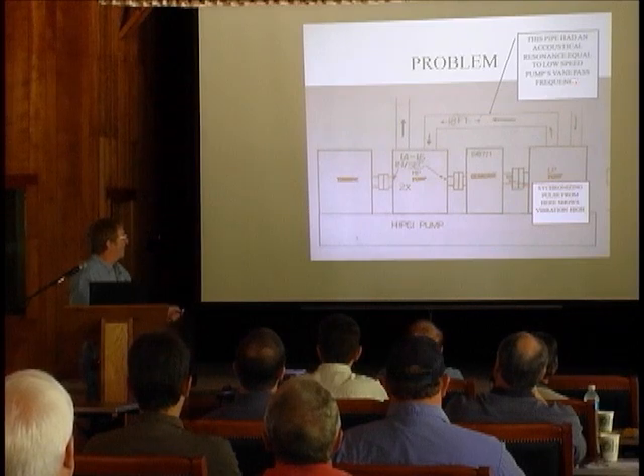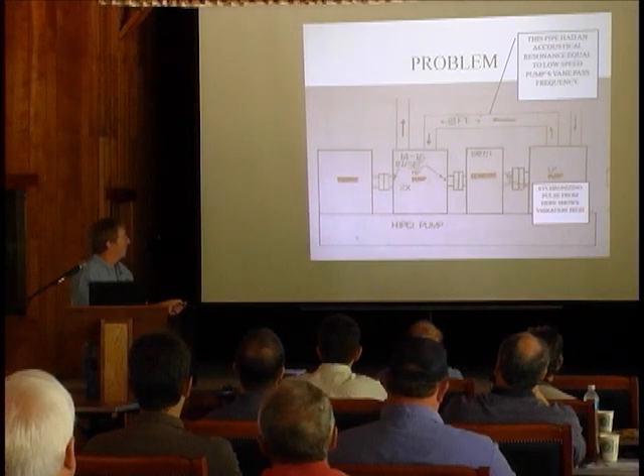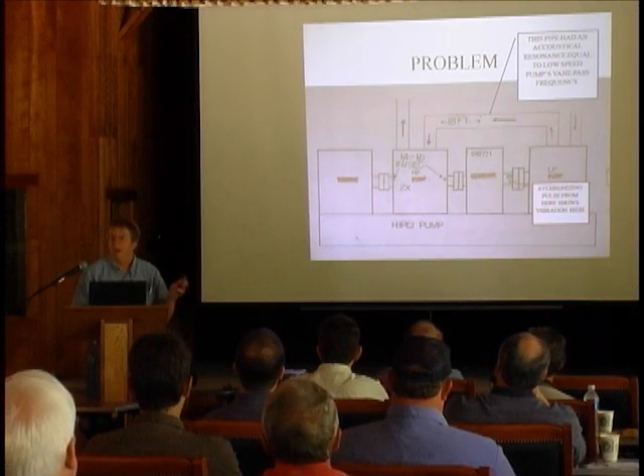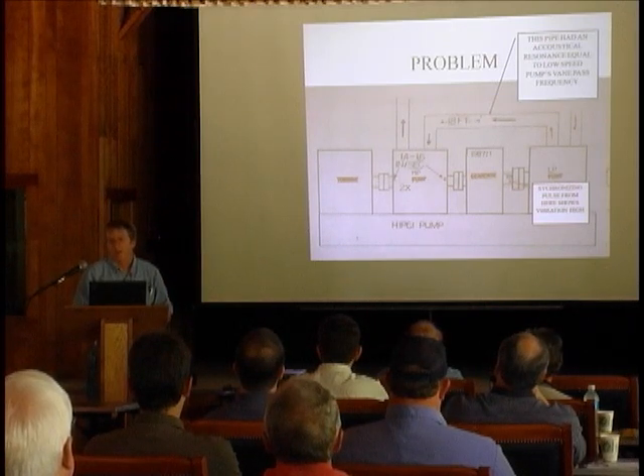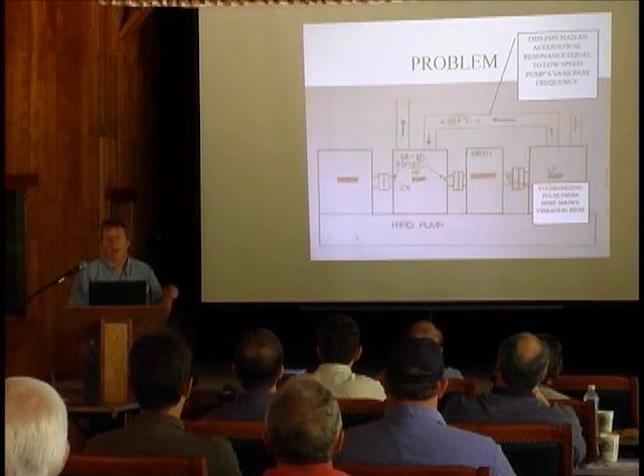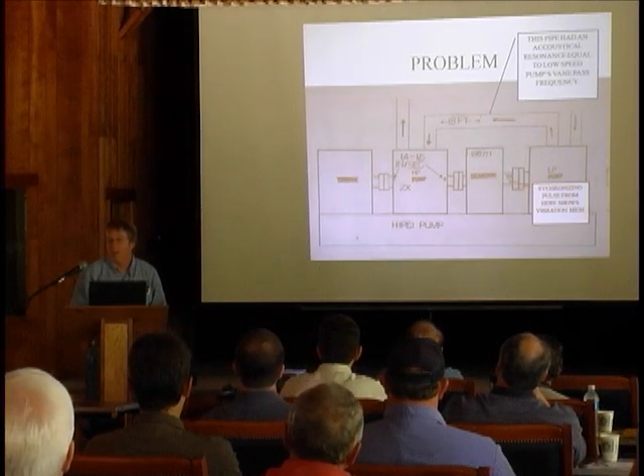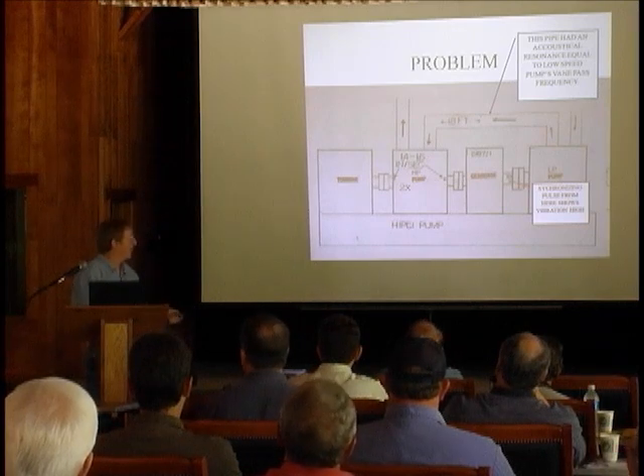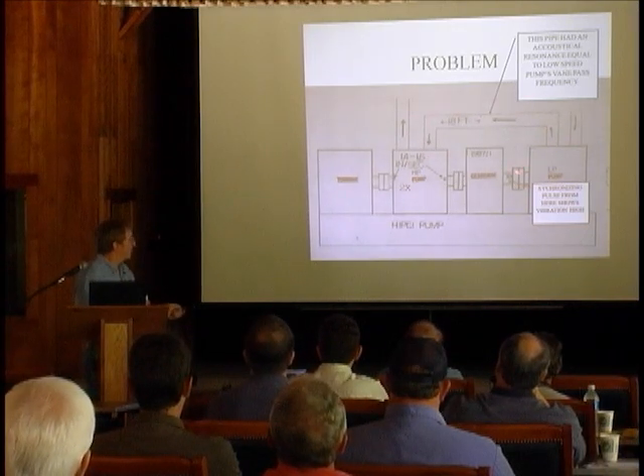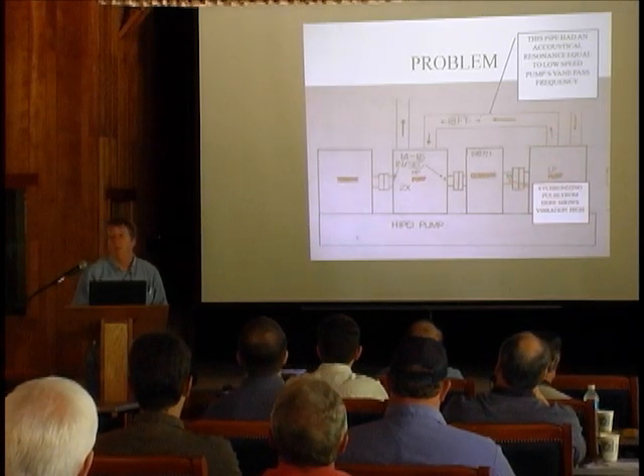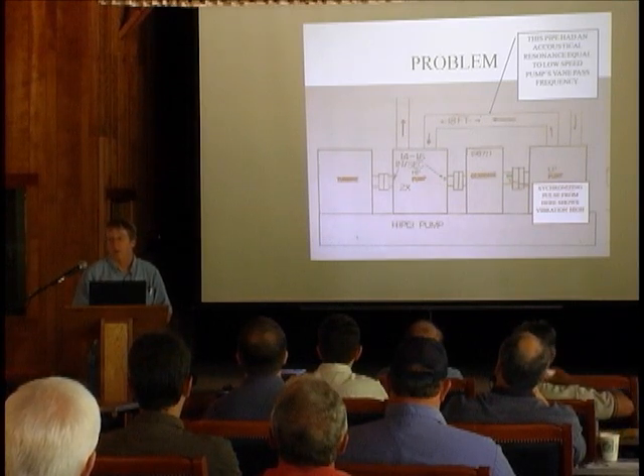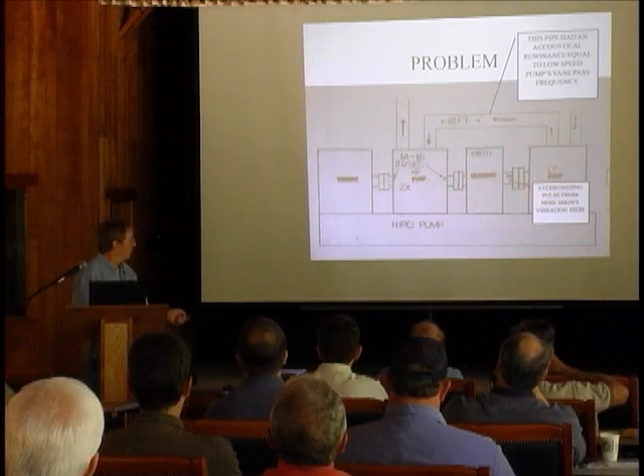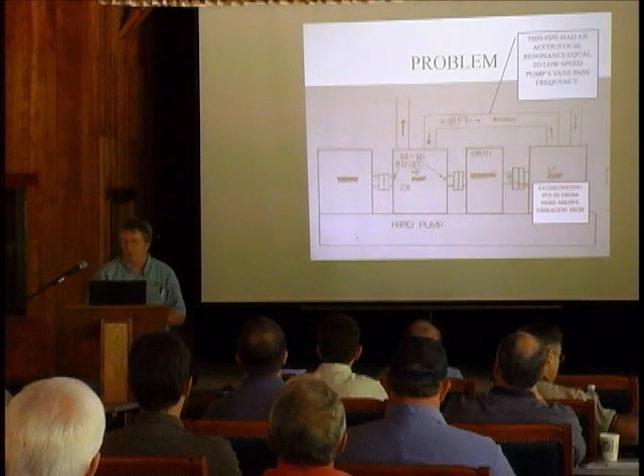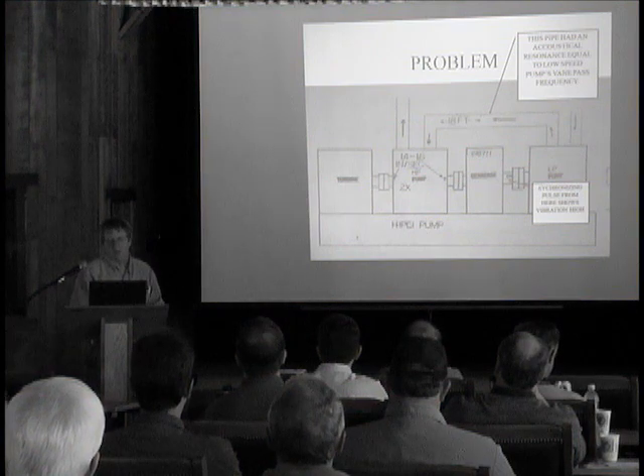But it turns out that when we measured and did all this, there was acoustical resonance equal to the low speed pump's vane pass frequency right in this speed range. And we also found out it would cycle with seasons when we had a little bit different temperature on the suction water. Everything matched up. It was actually an acoustical resonance taking the pressure pulsations from the low pressure pump that was exciting a horizontal natural frequency on the high pressure pump. Solution: change the number of vanes from 4 to 5. Took care of it. So that problem sort of goes on.